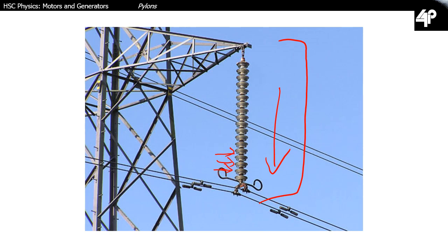Now, an old rule of thumb used to be that each disc typically is going to insulate around about 11 kilovolts, which is 11,000 volts. So if you were to see an insulator with 3 discs, then you would be insulating against a 33 kilovolt voltage that's flowing through the line. If you're looking at power lines that have recently been installed or upgraded, they might not be following this old pattern because new insulator designs have come along and they've changed over time. So some insulators you might see are still the old glass or ceramic types, but there are new polymer ones which have got different properties.